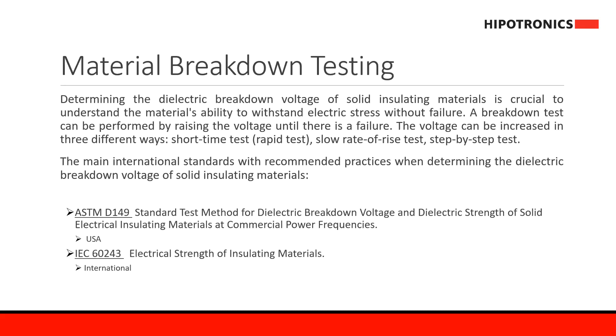The main standards followed for this type of testing are the ASTM D149 and the IEC 60243. The ASTM D149 is mainly followed in the US, while the international community uses the IEC 60243 standard as a guideline.